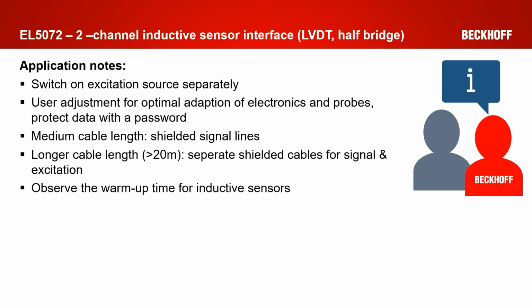Finally, some application notes from my side. So after setting all the parameters inside the EL5072 correctly, including the excitation frequency and the excitation voltage, please switch on the excitation source separately, because in the default state the source is off. To achieve an optimal adjustment of your electronics and the inductive probe, and to achieve a better accuracy, please use the user adjustment and protect your data via password.